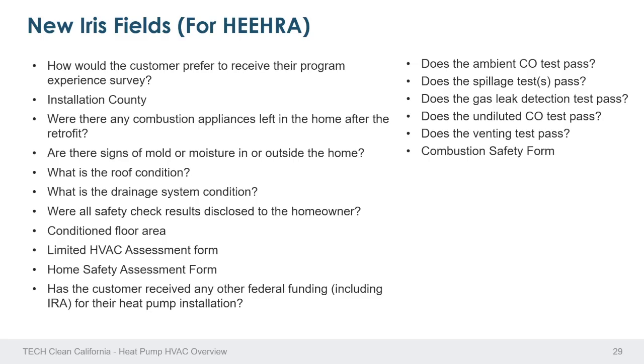Does the ambient CO test pass? Does the spillage test pass? Does the gas leak detection test pass? Does the undiluted CO test pass? Does the venting test pass? These are part of the combustion safety form.